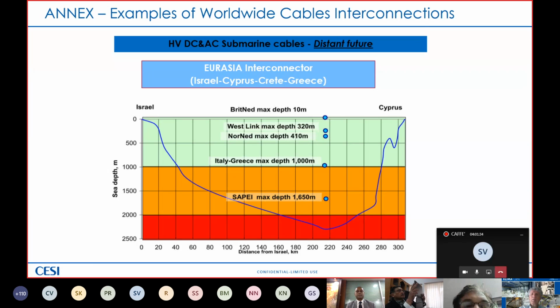The BritNed interconnection is the one in the North Sea, from the Netherlands to Britain. The maximum depth over there is in the range of 10 meters. So this is a good reason, first of all, to install offshore windmills, because it's quite easy, but also to use submarine cable that does not need the complicated design of a high depth situation.